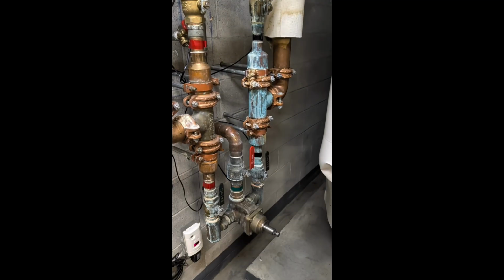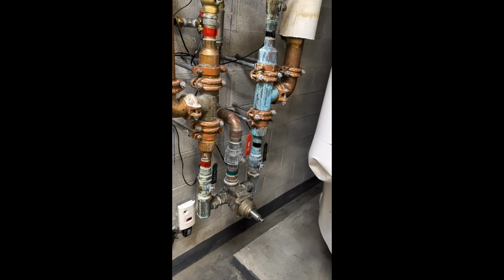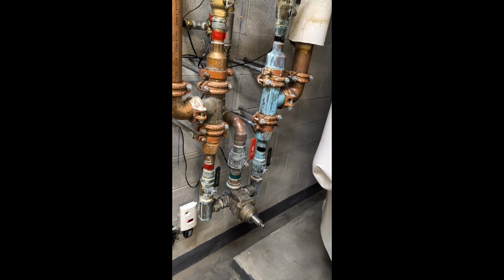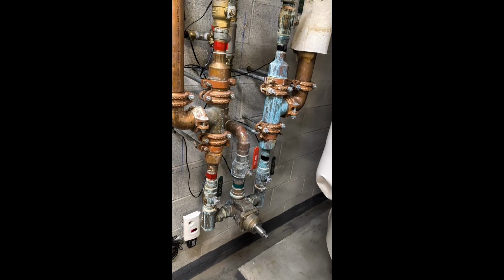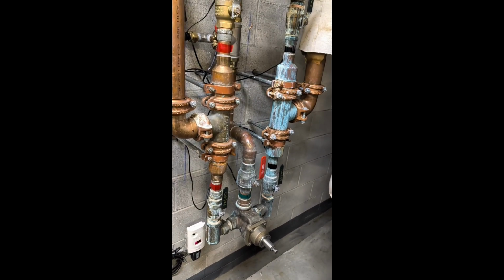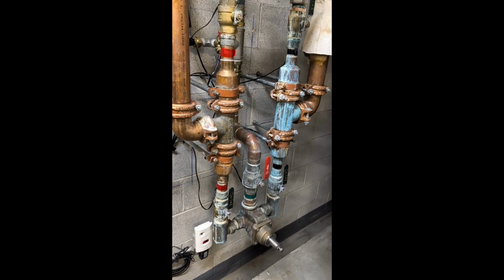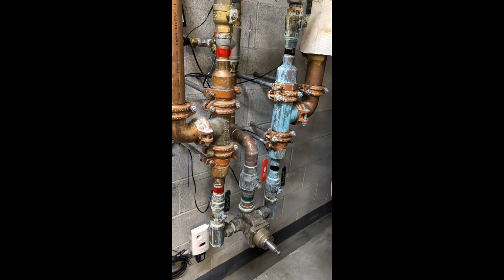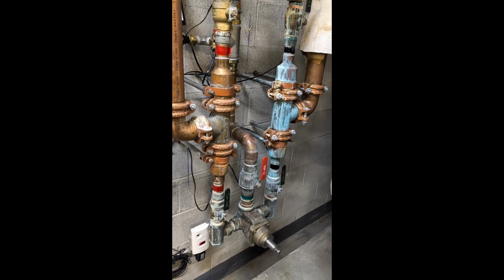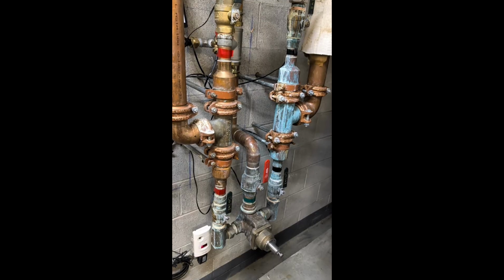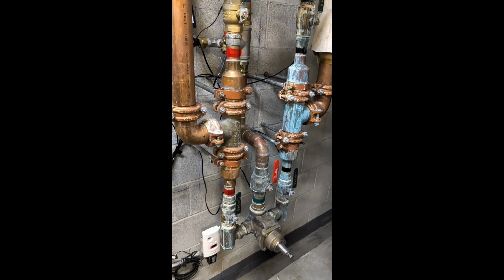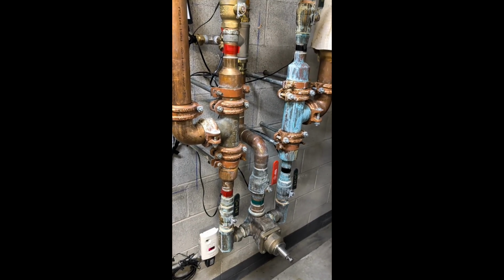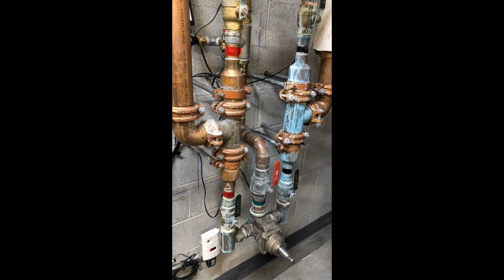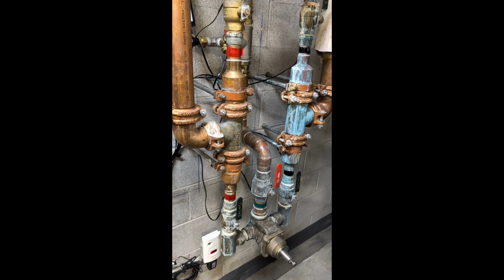What we're looking at is 2 mixing valves that mix hot and cold water to supply domestic hot water at the proper temperature. These valves can be quite problematic. We found that if we monitor the temperature of the inputs and outputs over time, it lets us make sure they're running properly, identify when they're not, and make adjustments to get them working as they should.